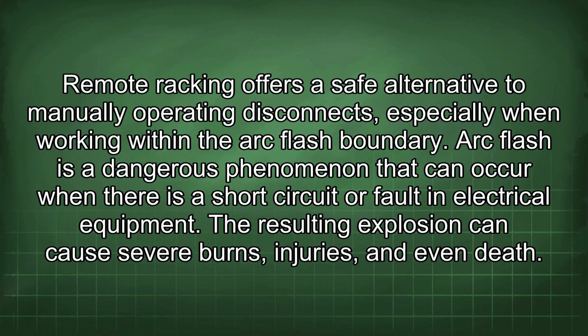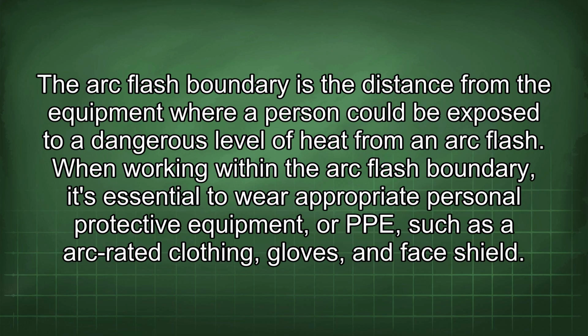Arc flash is a dangerous phenomenon that can occur when there is a short circuit or fault in electrical equipment. The resulting explosion can cause severe burns, injuries, and even death. The arc flash boundary is the distance from the equipment where a person could be exposed to a dangerous level of heat from an arc flash. When working within the arc flash boundary, it's essential to wear appropriate personal protective equipment, or PPE, such as arc-rated clothing, gloves, and face shield.